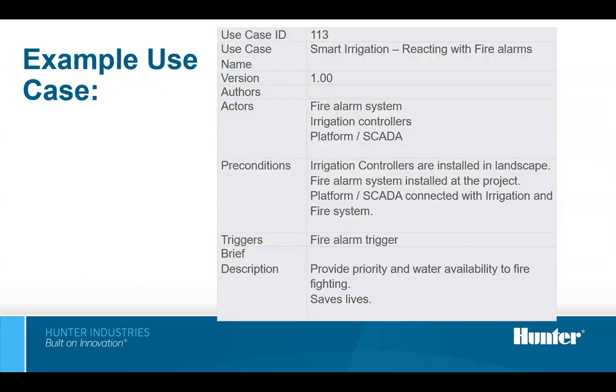This is an example of a form we use for a use case, and this is one that comes up a lot: reacting with fire alarms. The fire alarm system is already present in the SCADA system, and that's very common. When the fire alarm goes active and there is a fire, we want to immediately terminate all irrigation, and this can be automated. That allows all the pressure and flow to be available to the firefighters.